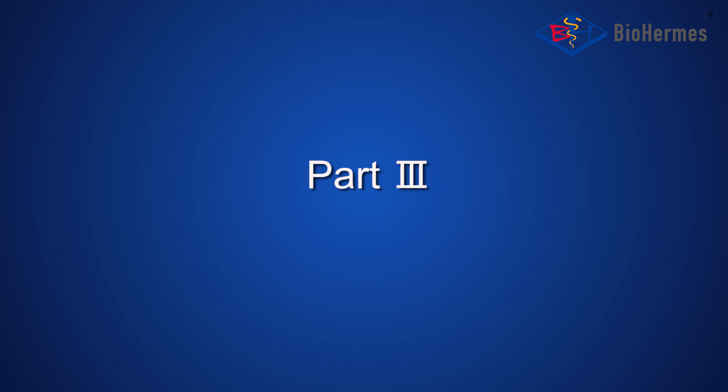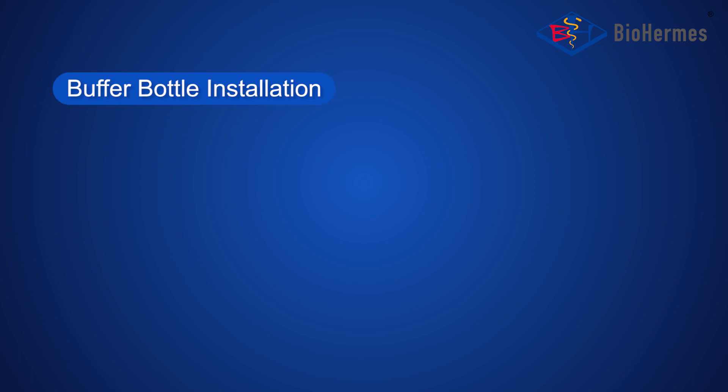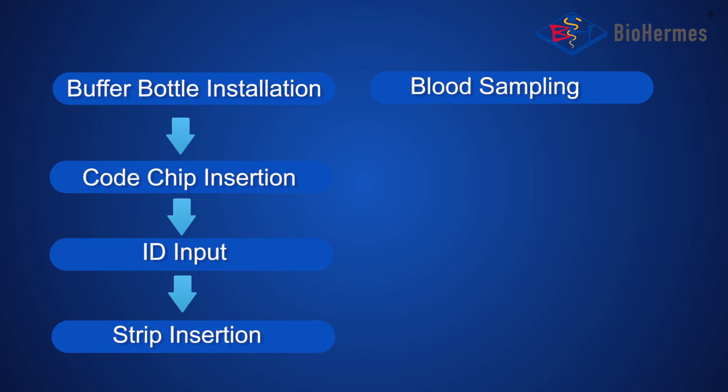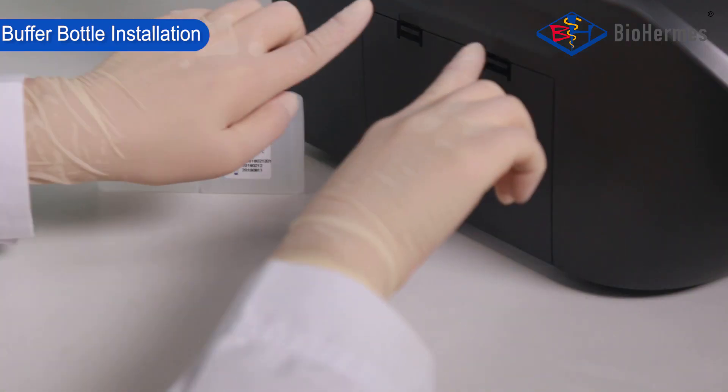Part 3: HbA1c Testing. The Testing Procedure includes: Buffer Bottle Installation, Code Chip Insertion, ID Input, Strip Insertion, Blood Sampling, Blood Adding, and Result Reading.